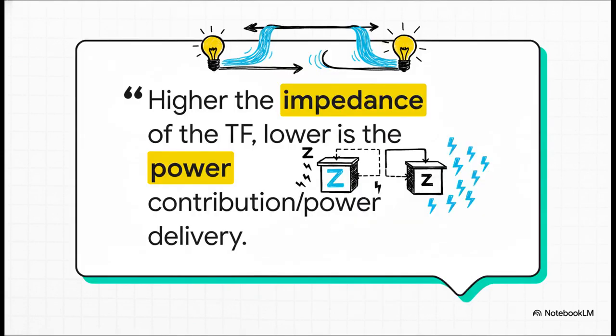So what's the bottom line here? It's simple: the transformer with the higher impedance does less work. You can think of electricity like water - it's always going to follow the path of least resistance, or in this case, least impedance. So the transformer with the lower impedance is the one that's going to take on more of the load and do the heavy lifting. And that's exactly why getting their impedances matched is so important if you want them to work together nicely.